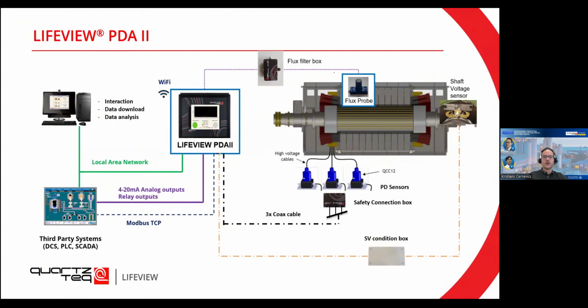You can install Wi-Fi and connect it through Wi-Fi. You can connect it through a local area network through an Ethernet cable. There's also the possibility of integrating the signal of the 4 to 20 milliamp analog outputs or relay outputs to your existing third-party systems, such as SCADA. You can also use Modbus TCP. So once again, depending on your needs, depending on the existing infrastructure and systems, there are many possibilities of how we can integrate these online measurements into your existing systems. So you don't need to build something completely new.